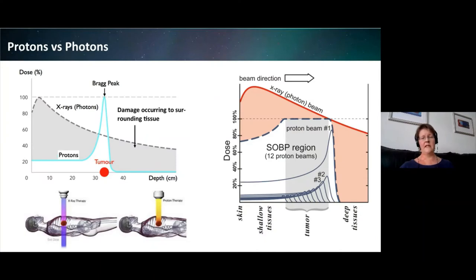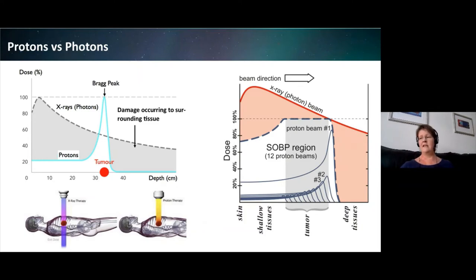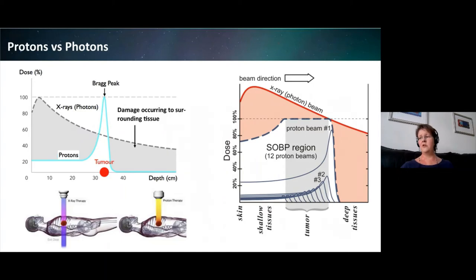Why do we want to use protons for radiotherapy? The success of the therapy relies on the physical properties of protons and in particular the way they deposit their energy in materials. While moving through material, proton beams release only a little of their energy as they travel, but then release almost all of their energy when they come to rest. This is known as the Bragg peak effect. The fact that protons deliver almost all of their energy at a depth dependent on the initial beam energy means that in radiotherapy, the dose delivered to tissue outside of the tumour volume is much lower than with conventional x-ray and electron beam therapy.